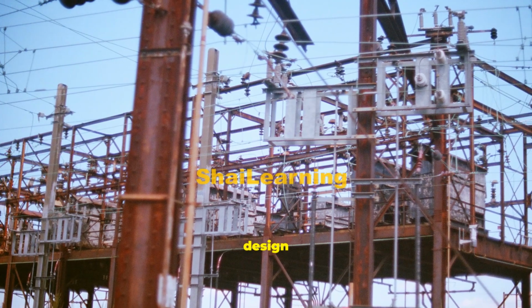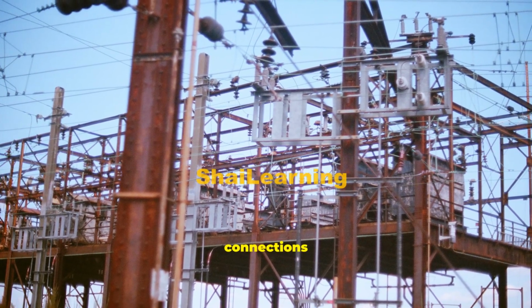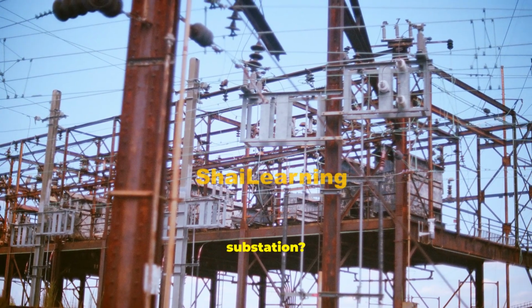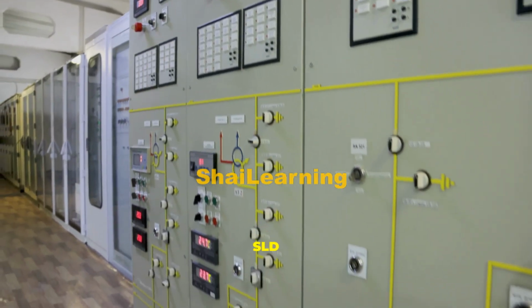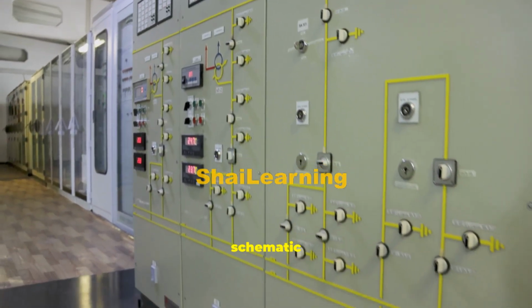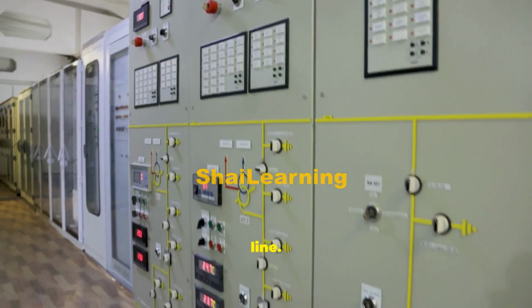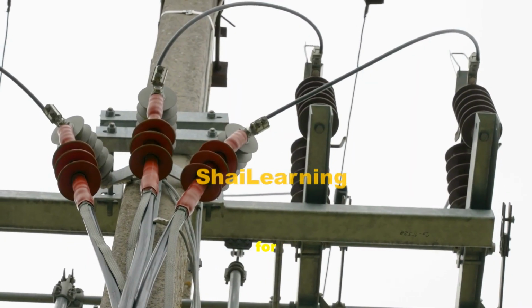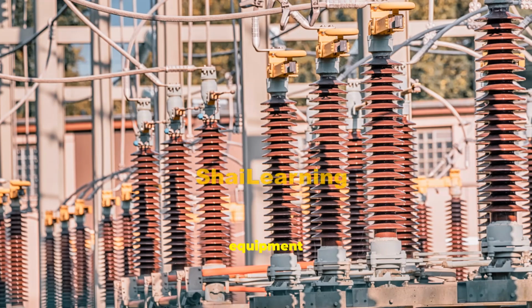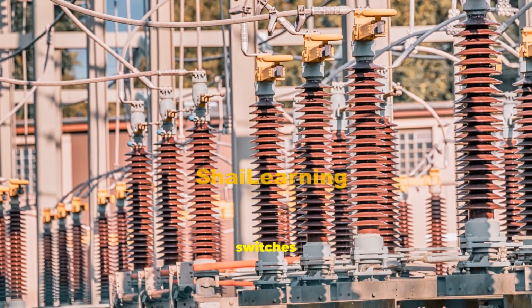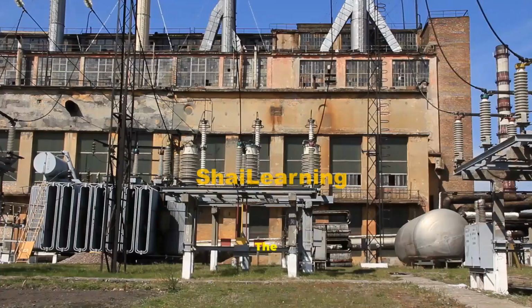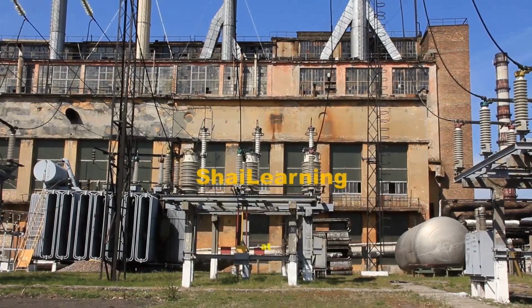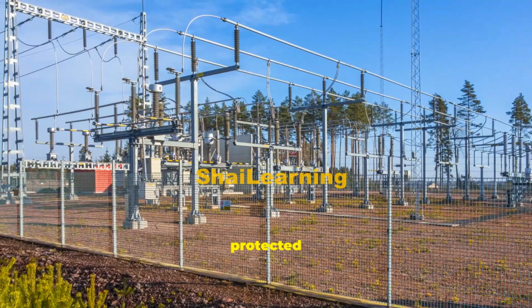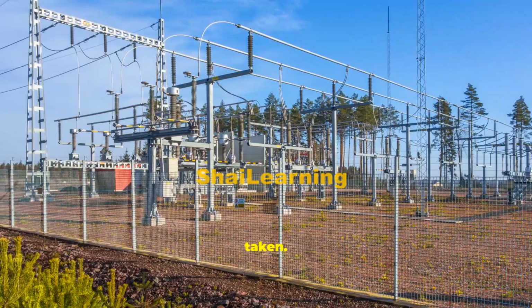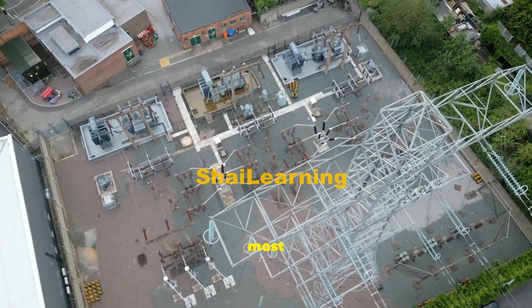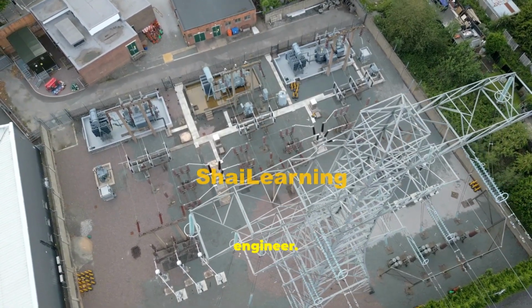How do engineers design and understand the complex web of connections inside a substation? They use a single-line diagram, or SLD, a simplified schematic representing a 3-phase system with one line. It's the master blueprint for a substation. It shows major equipment, transformers, circuit breakers, and switches, and how they connect. The SLD makes power flow paths clear at a glance. It shows how sections are protected and where measurements are taken. Learning to read an SLD is one of the most important skills for any power engineer.